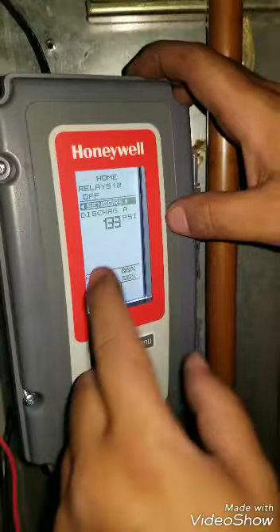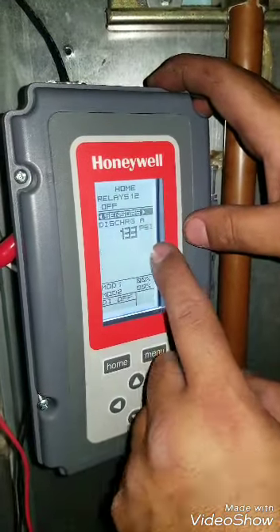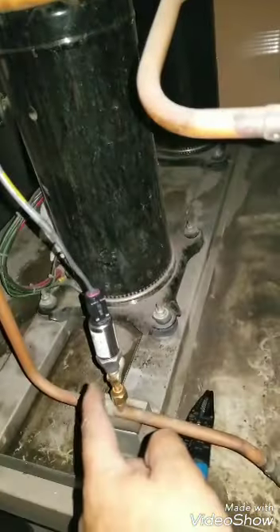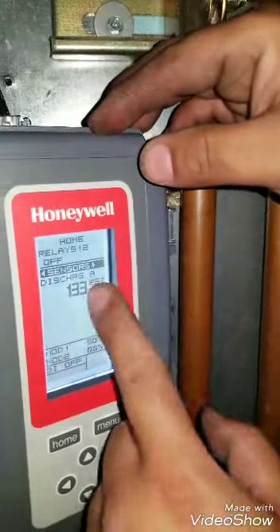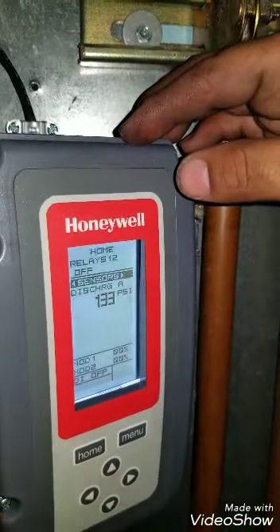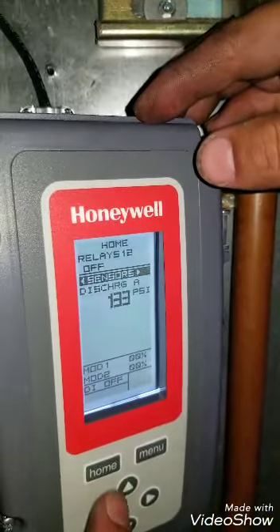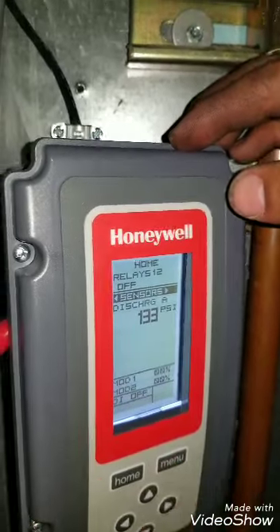So when you hit home, 133 PSI, that's the pressure that the transducer is reading from the line. So that's the refrigeration pressure, 133.